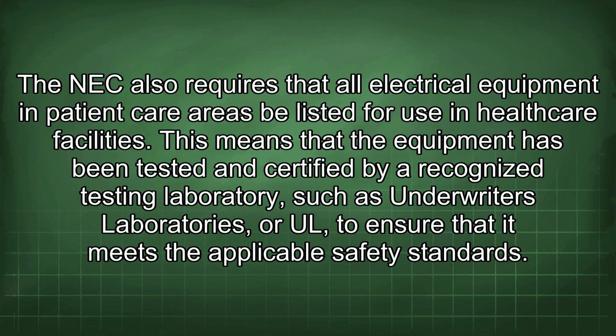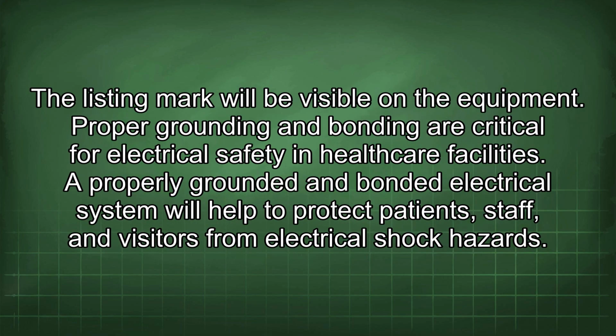The NEC also requires that all electrical equipment in patient care areas be listed for use in healthcare facilities. This means that the equipment has been tested and certified by a recognized testing laboratory such as Underwriters Laboratories, to ensure that it meets the applicable safety standards. The listing mark will be visible on the equipment.